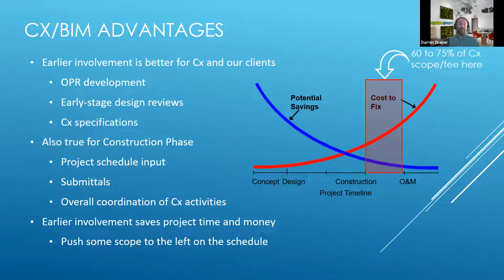Earlier involvement in the construction phase is important too. We want to give feedback on the construction schedule early, ensuring functional performance testing and related activities like test and balance, controls, equipment startup, energization, and building drying are fully addressed. We clarify how that impacts our commissioning effort, review submittals, and establish overall coordination of commissioning activities early in the process.